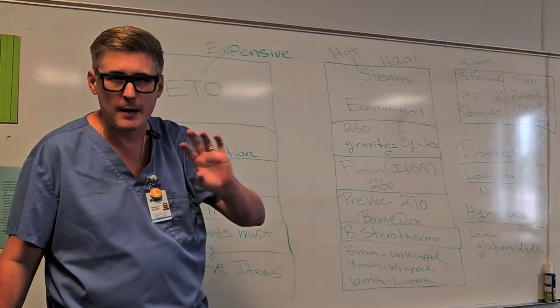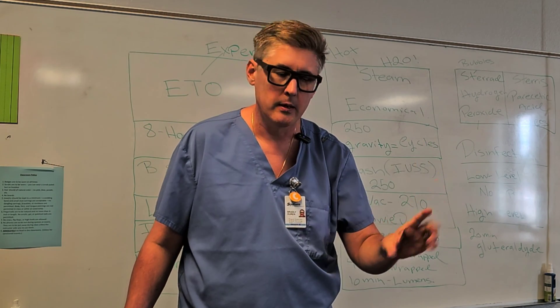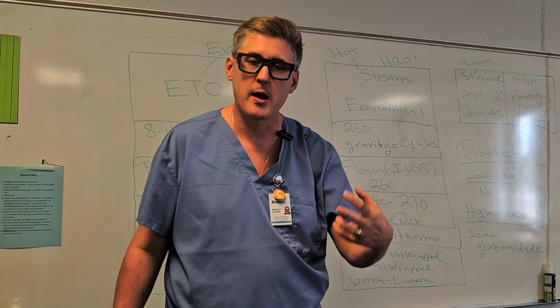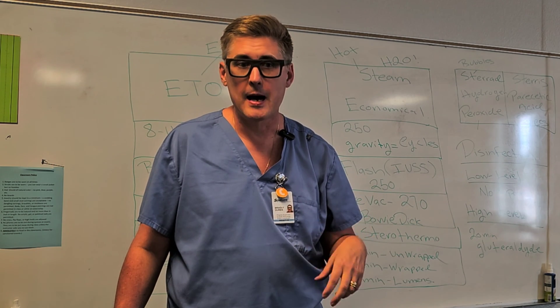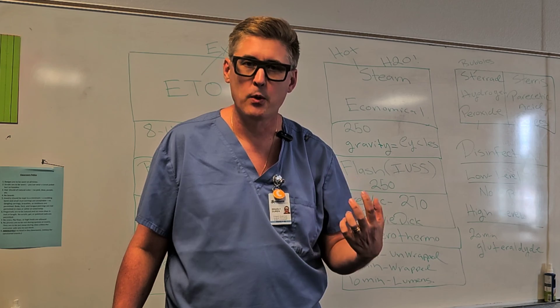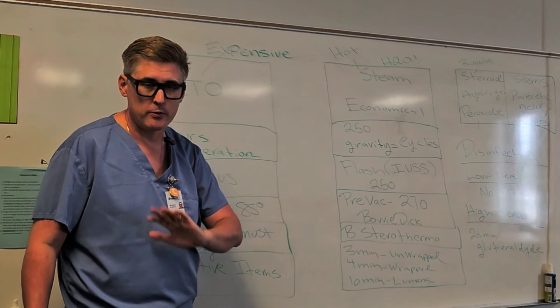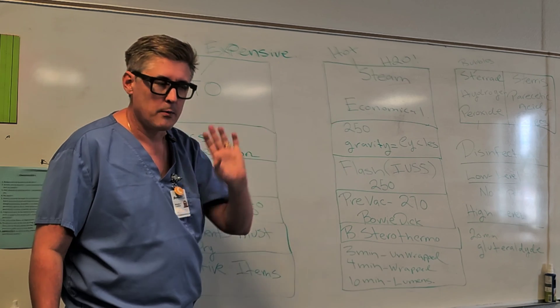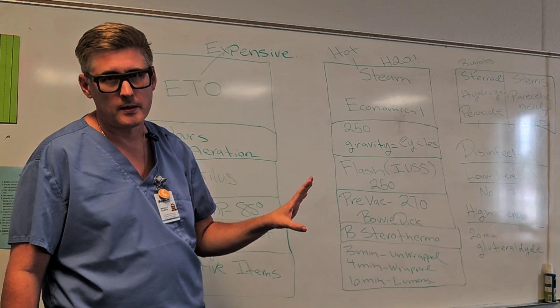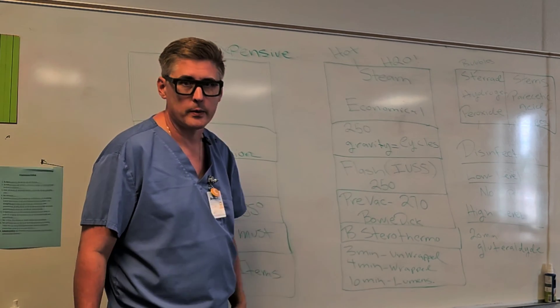Biological indicator. Don't confuse that with a chemical indicator, which are tape or little things within trays to verify that it's been processed. Believe it or not, it's not the most reliable way as a chemical. It's a biological. Chemical is just verified it's been through a process. The most reliable way to prove something that's sterilized is a biological indicator.